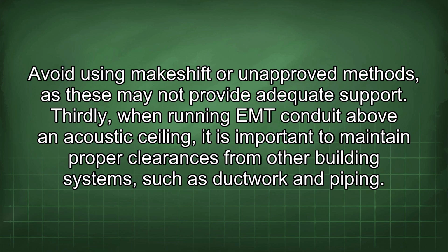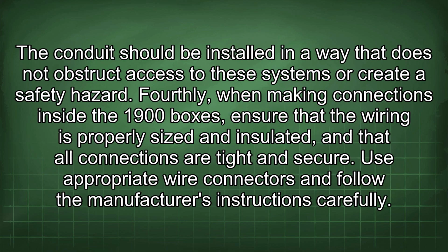Thirdly, when running EMT conduit above an acoustic ceiling, it is important to maintain proper clearances from other building systems, such as ductwork and piping. The conduit should be installed in a way that does not obstruct access to these systems or create a safety hazard. Fourthly, when making connections inside the 1900 boxes, ensure that the wiring is properly sized and insulated, and that all connections are tight and secure. Use appropriate wire connectors and follow the manufacturer's instructions carefully.